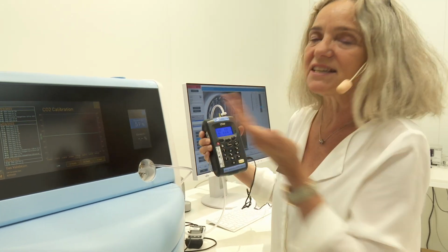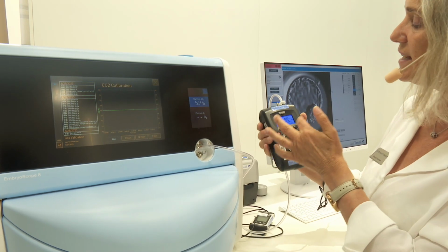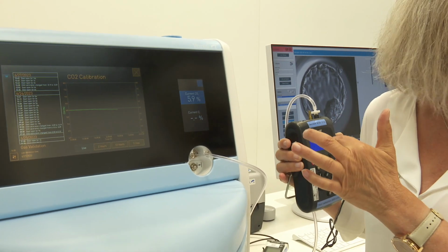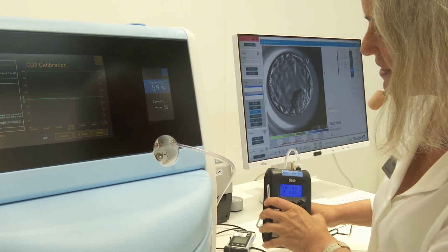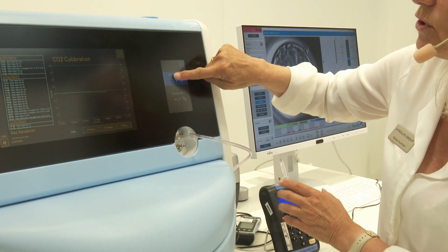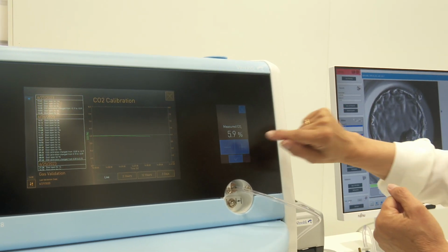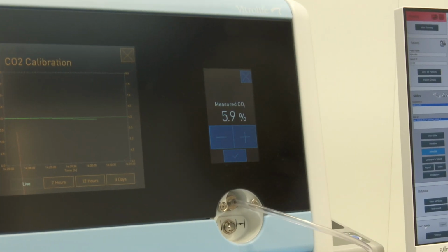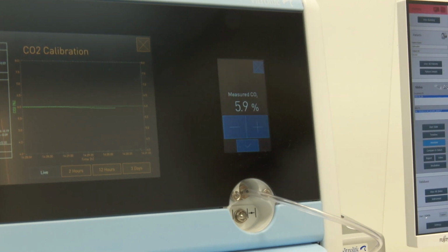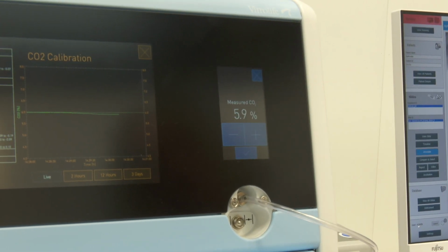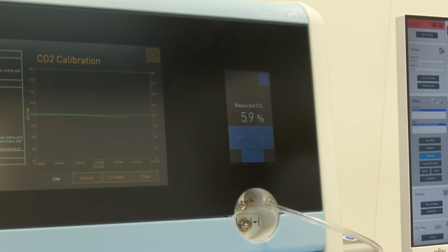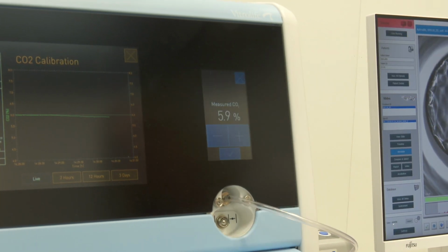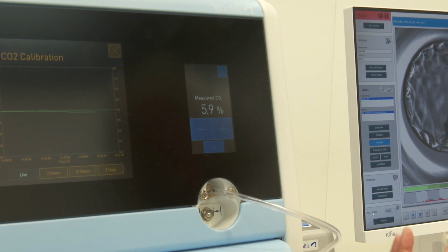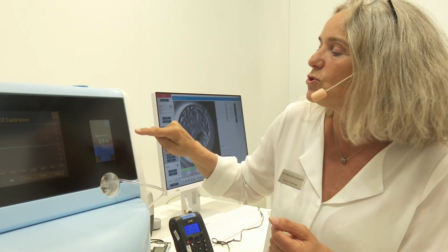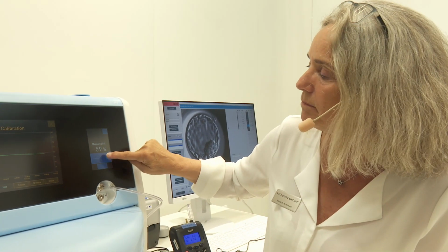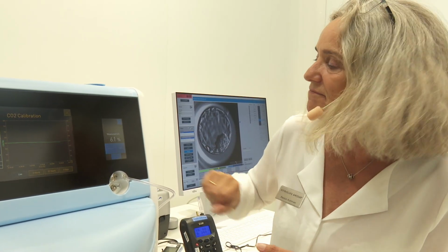Now it is absolutely the same. Or now it's taking in what it currently is. But let's pretend it was 6.2, and the set point is 6.0. So then you go in here and you press plus, because it moves 0.1 for each step. Now this is the measured CO2 by the sensors inside, so very soon it will be at 6%. So in that case, it was 6.2. I will press 2 times on here. Now we just do it for demonstration.